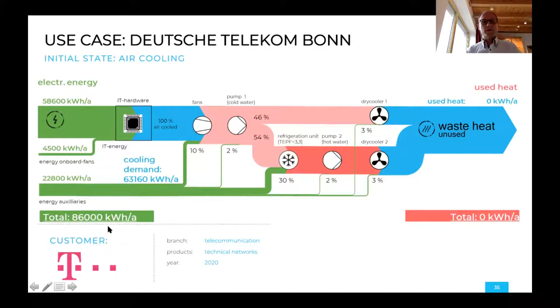I added also to this presentation a more detailed look at where the energy typically goes. We have a comparison here between the air-cooled system and how that typically works. I'm not going into all details, but you see that a lot of the electricity comes in, and that's basically converted to air, to warm air. With fans, it's moved out, and then it goes to the refrigeration part and generates waste heat. Even if you have some free cooling going to a dry cooler, it still needs a lot of electricity. Total: 86,000 kilowatt hours per year to run such a system.